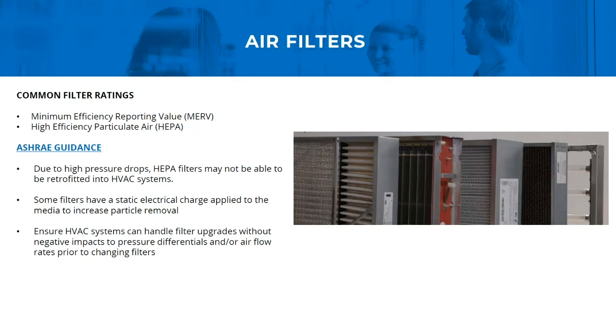So if your air handler can take a higher rated filter, we suggest that you do that. But I would start with filtration. That would be the first one that's recommended by the CDC and ASHRAE. And then from there, if you would like to add on to your filtration, increasing your outside air has been a big one from the CDC. I certainly would look into UVGI as well as needlepoint or bipolar ionization as additions to the recommended filter change. So to answer your question, unfortunately, there's not a one size fits all. Every building's built a little bit different, but I would start with filter increases first, and then look into the other three as options to help increase better indoor air quality. Excellent. Great point.